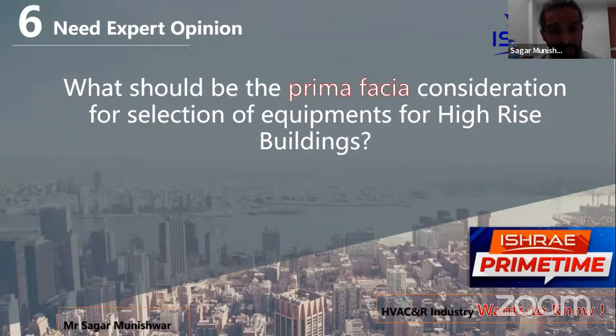Why I'm stressing these intermediate service floors is, as a designer, as HVAC engineers, we should insist on having those intermediate service floors. Yes, it's a cost to the client. The architect may not agree, but that's required for the system to run properly. So the consideration for selection of equipment for a high-rise building, yes, you need to take care of the pressure per se. There was one second question also, Imran.